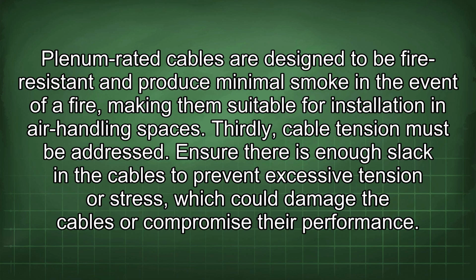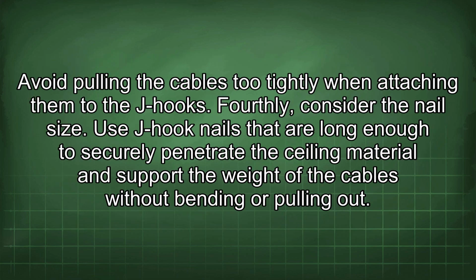Thirdly, cable tension must be addressed. Ensure there is enough slack in the cables to prevent excessive tension or stress, which could damage the cables or compromise their performance. Avoid pulling the cables too tightly when attaching them to the J-hooks. Fourthly, consider the nail size. Use J-hook nails that are long enough to securely penetrate the ceiling material and support the weight of the cables without bending or pulling out.